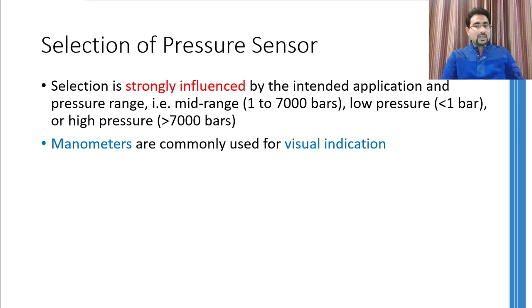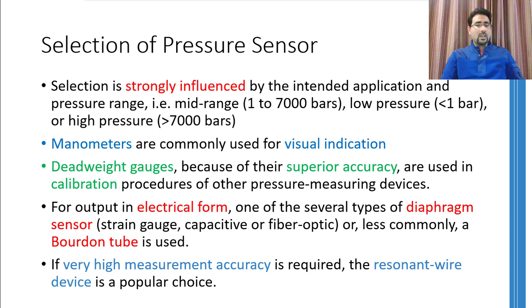Moreover, manometers are only used for visual indications, so they cannot be used as part of some automatic feedback control system. If you want to use the electrical output so that it can be fed to a control system, then your options are diaphragm sensors and Bourdon tube sensors. The sensors will have electronic displacement sensors in them that will measure the amount of expansion of the diaphragm or the Bourdon tube and will generate an electrical output corresponding to the displacement of the elastic element. Moreover, the resonant wire device is a popular choice if you want highly accurate pressure measurements.